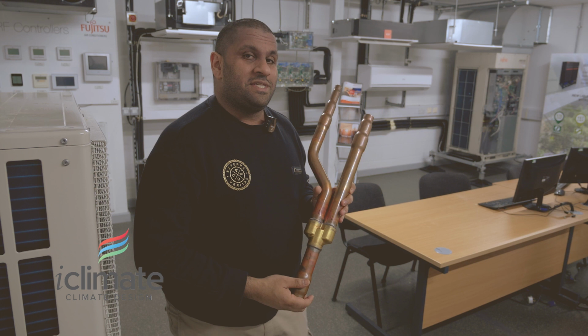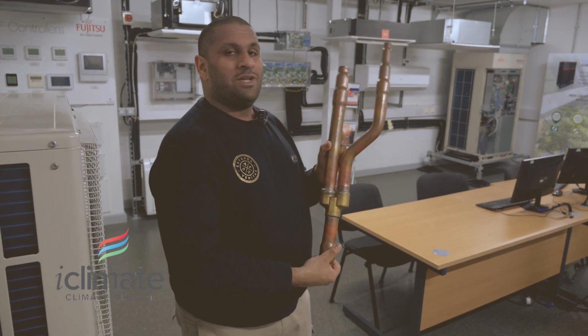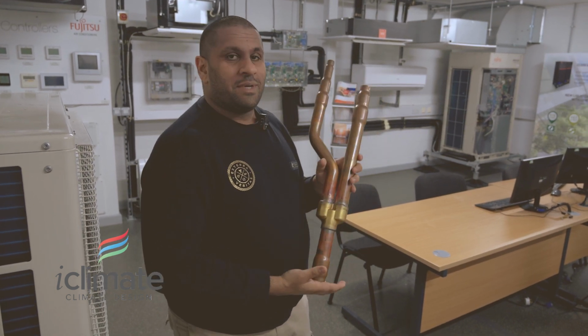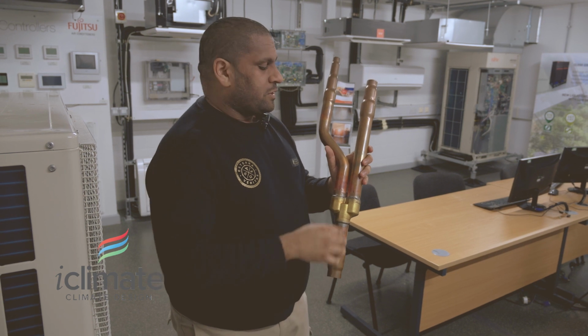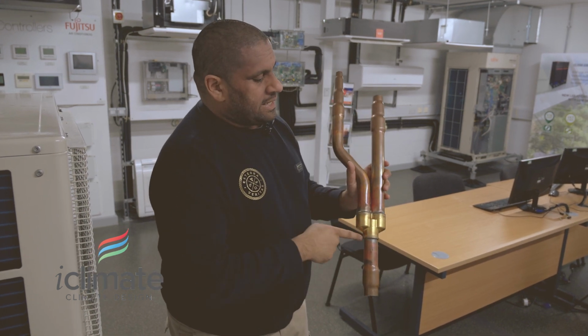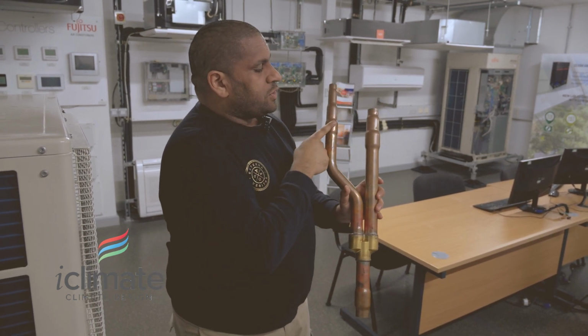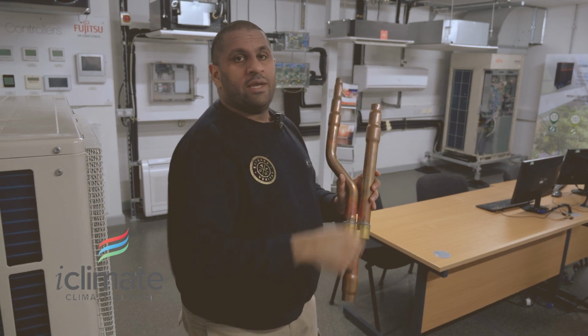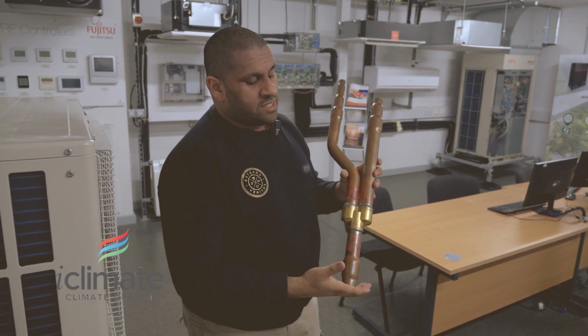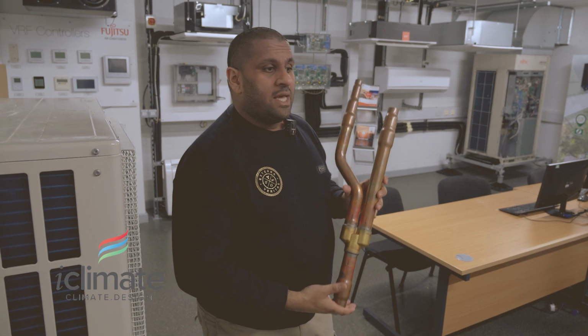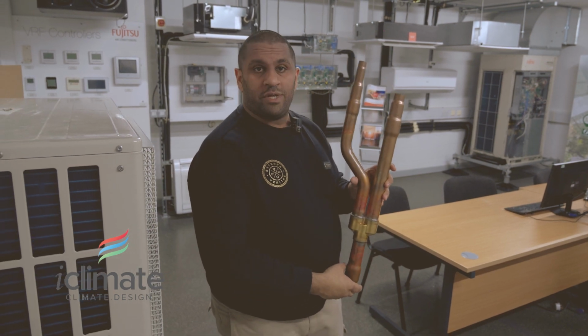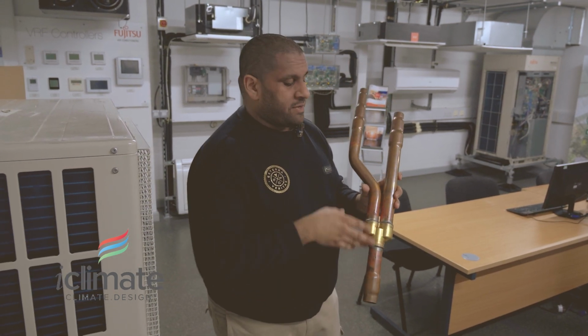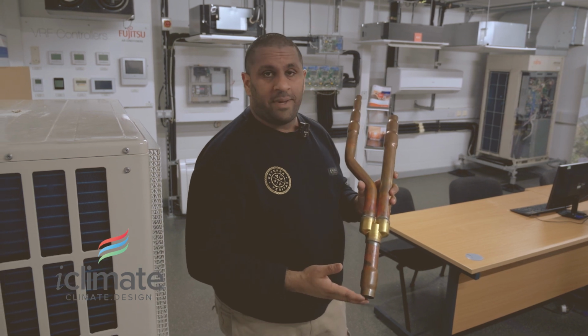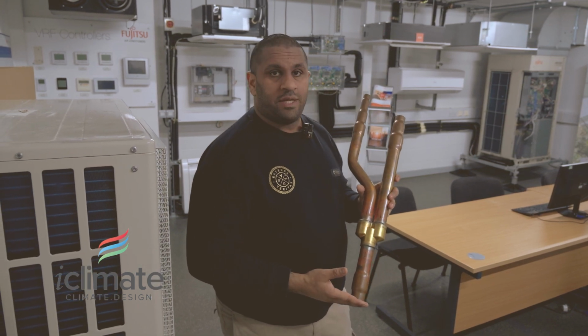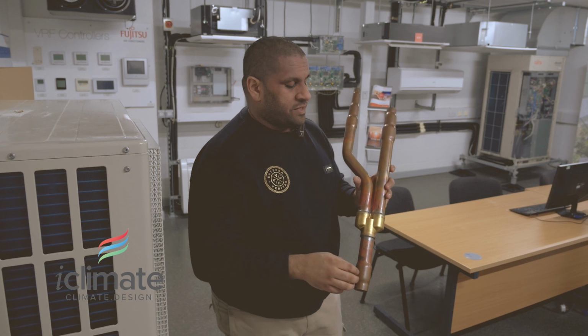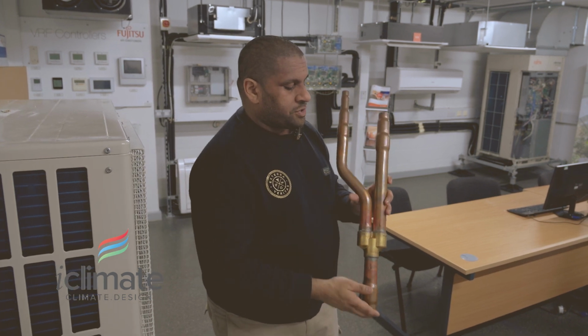When we referenced the pipe splits earlier, this is a huge, large scale pipe split in my hand, but essentially the pipe split orientation remains the same. Inlet into here, an outlet to a fan coil unit, and the existing ring that goes to the other fan coil units. This is for the VRF application, and this branch needs to be put in a specific orientation, but obviously this is a very large branch for a very high capacity, large commercial air conditioning system. And for the residential units, there'll be a much smaller branch.